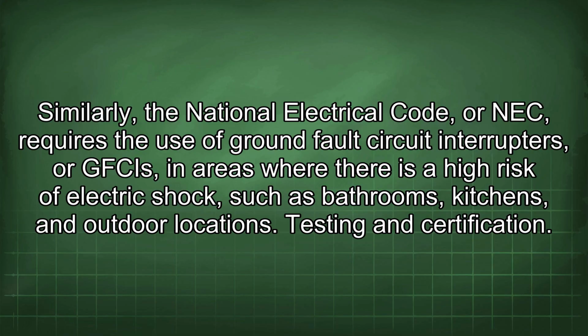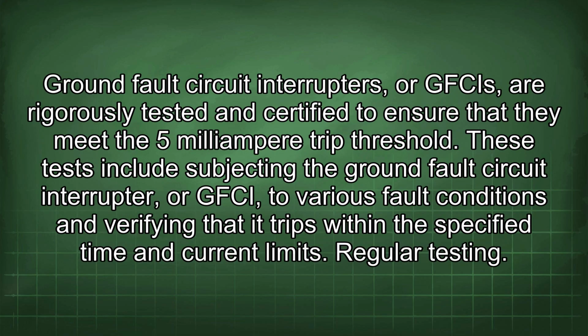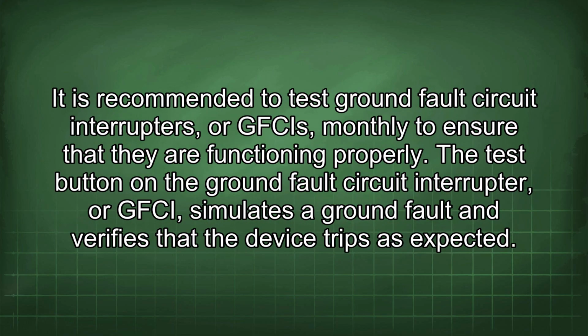Testing and certification. GFCIs are rigorously tested and certified to ensure that they meet the 5 mA trip threshold. These tests include subjecting the GFCI to various fault conditions and verifying that it trips within the specified time and current limits. Regular testing. It is recommended to test GFCIs monthly to ensure that they are functioning properly. The test button on the GFCI simulates a ground fault and verifies that the device trips as expected.